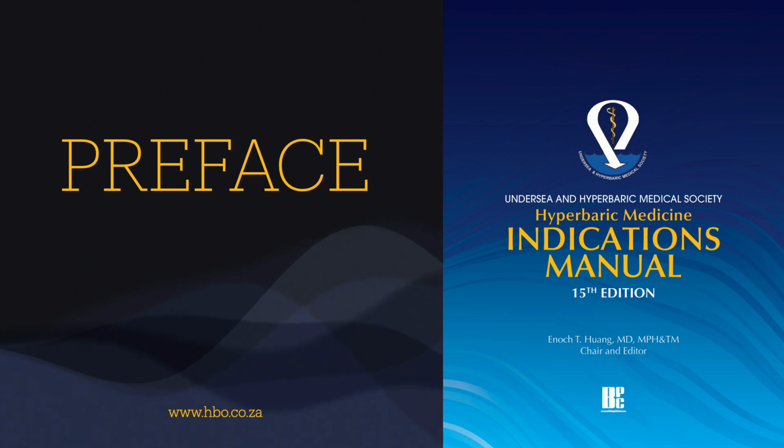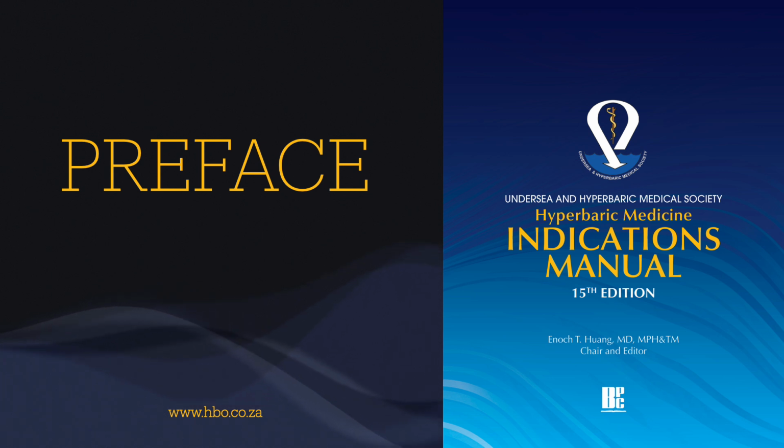So the manual gives a simple definition. Yep, hyperbaric pressure can just be stated as hyperbaric, meaning any atmospheric pressure above the normal pressure found at sea level. And normal average sea level pressure is defined as 760 millimeters of mercury, or 1 atmosphere absolute, 1 ATA. The manual gives the conversion to kilopascals as 101.325 kPa. It acknowledges that pressure varies with weather and altitude, so you need that standard reference.